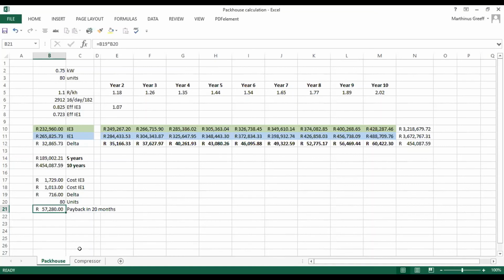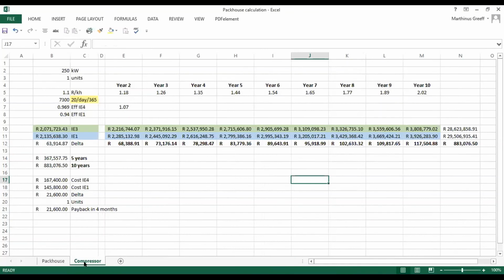Then, as the lady Andre just mentioned, I went to look at the compressor, because pack-outs only work for a certain period, but we need to cool the pack-outs or storage facility. I worked on an average size of one 250 kilowatt motor, same tariff, working 20 hours per day for a year. I looked at efficiencies between the IE4 and IE1, and as we can again see, it's about 2.9% difference.